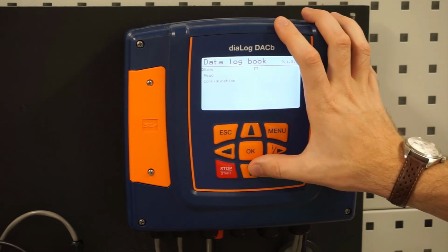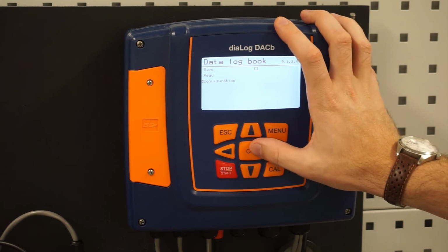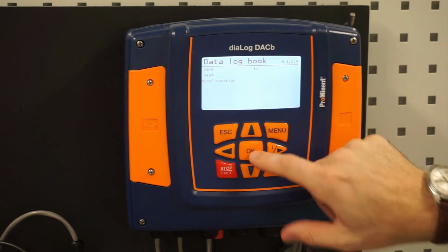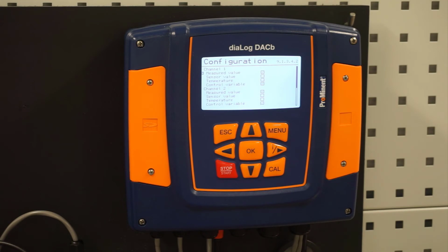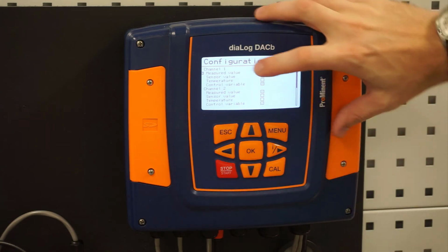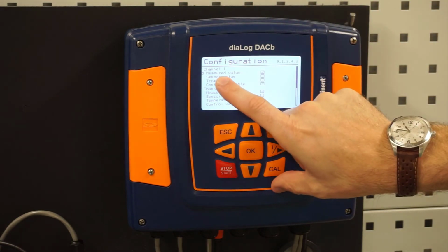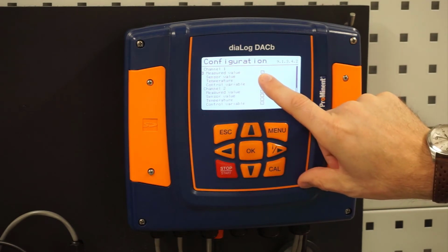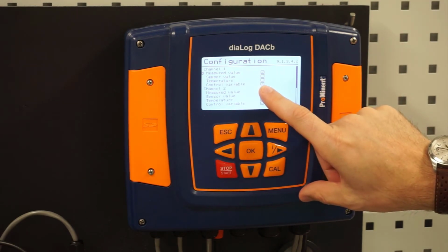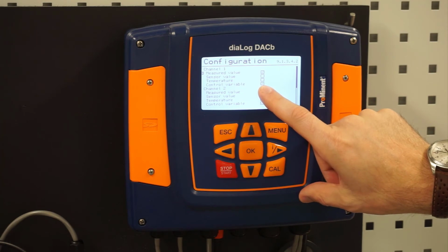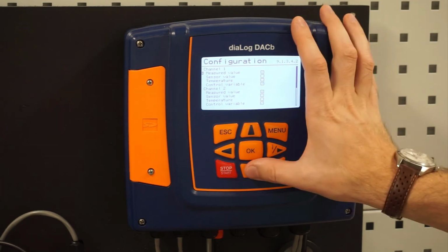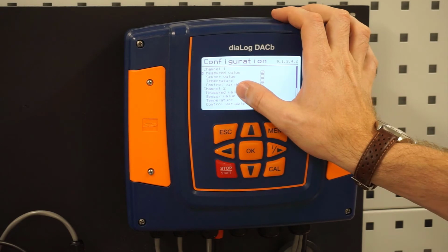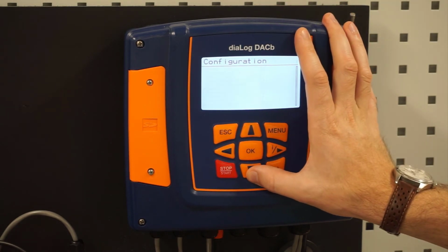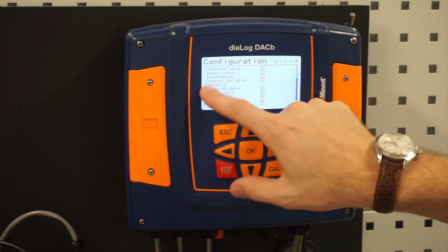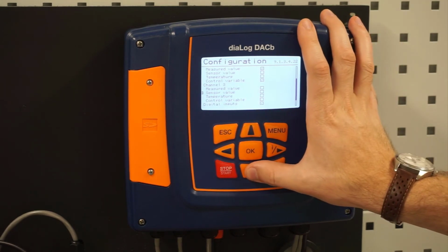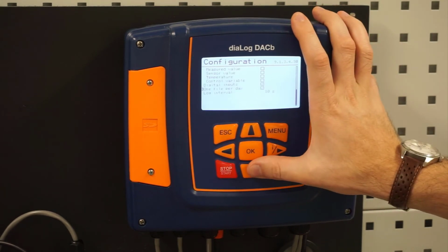Data needs to be set up if you want to log the data. So I go to configuration, and then there's a whole bunch of things I can check. Right now, we are logging the measured value on channel 1. We are also getting the control variable. We are getting the measured value and the control variable on channel 2. Channel 3, we don't have anything on there, so it's all set off. Our digital inputs are being looked at and logged.